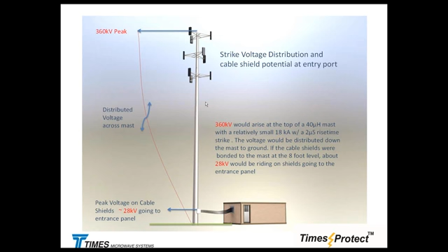So we are going to experience a different inductive voltage drop on the tower, on the cable, and on the grounding kits. The good thing that works for us is that the tower, because of its massive size, in a well-grounded tower environment will take in the range of 60 to 70% of the current down. If you look at a monopole or three-legged tower, the J bolts hold everything into the foundation, and the rebar inside is very well connected. So that tower is going to be the best conductor we might have. The question is, what are we going to do to enhance that in the soil around the tower? I've got some slides to show you later on.